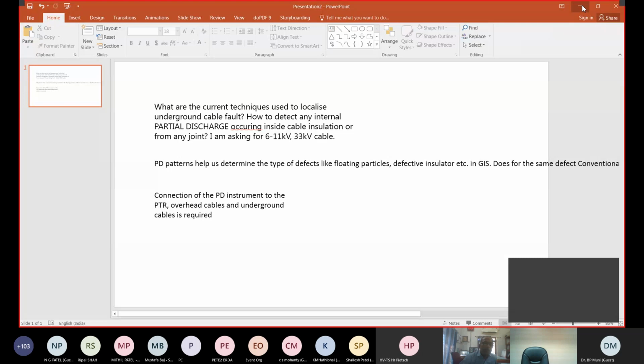If it's an after-installation test, then of course it's offline. If you do it online, you have two disadvantages. First, you have the same frequency, and unfortunately you cannot change the voltage. What does that mean? If you're offline and you change the voltage, you get the inception and extinction voltage of the PD, which gives very helpful information about what kind of defect you have.